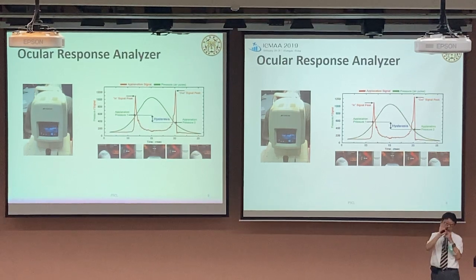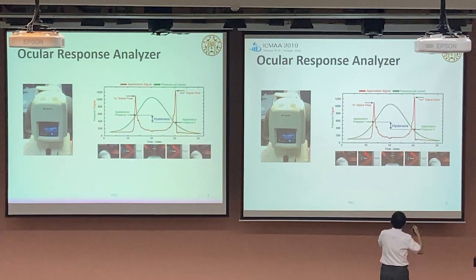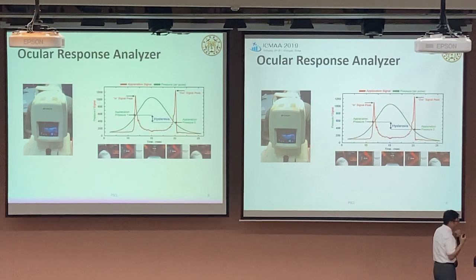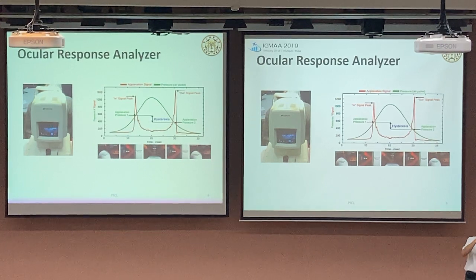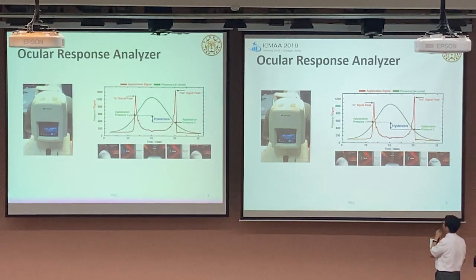When the jet touches your eyeball, the cornea starts to deform, and the laser gets picked up, so the position of the laser also starts to bend toward the extreme point. After the air drops, you see a rise. The cornea bounces back, and the laser bounces back. So you can pick up this signal, and that gives you a lot of information. For example, when it started to bend, and how deep does it bend? Also, the difference between the undeformed cornea position and the deformed cornea position. So you have a lot of indexes you can use.